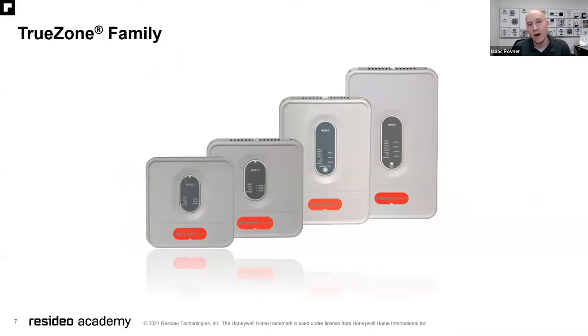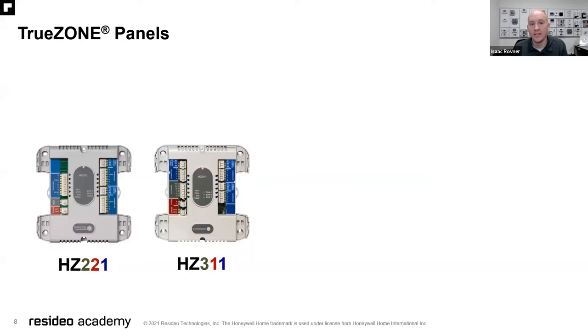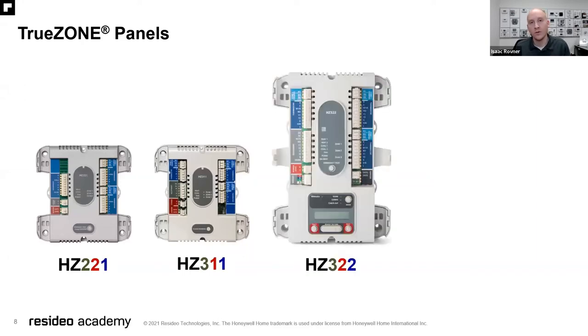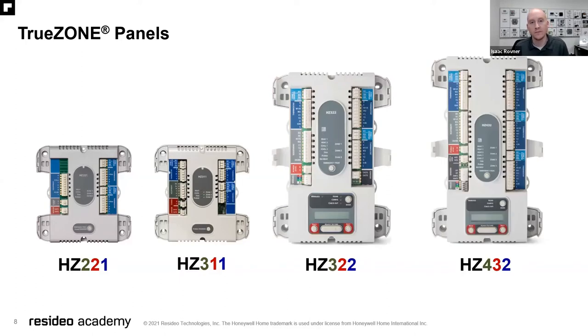We have a product that fits every application, whether using a heat pump with or without backup, or a multi-stage conventional system. We have our HZ221, HZ311, HZ322, and HZ432. All you have to remember is that first number after the HZ — HZ stands for Honeywell Zone. The first number indicates the number of zones that panel is capable of. For example, the HZ322 is capable of controlling up to three zones, while the HZ432 can do up to four zones.